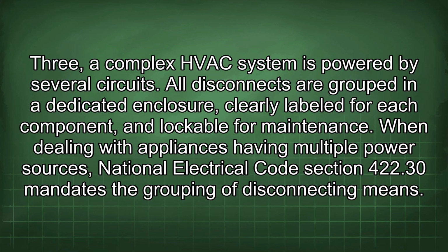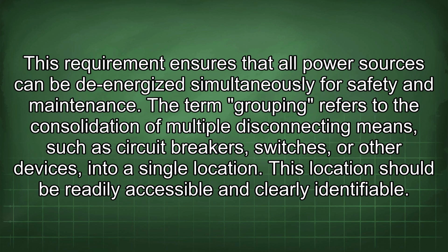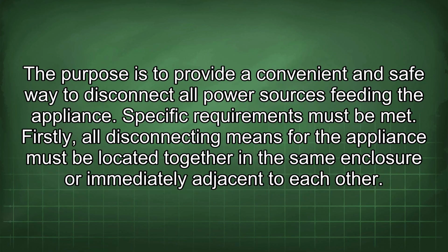When dealing with appliances having multiple power sources, National Electrical Code Section 422.30 mandates the grouping of disconnecting means. This requirement ensures that all power sources can be de-energized simultaneously for safety and maintenance. The term grouping refers to the consolidation of multiple disconnecting means, such as circuit breakers, switches, or other devices, into a single location. This location should be readily accessible and clearly identifiable. The purpose is to provide a convenient and safe way to disconnect all power sources feeding the appliance.